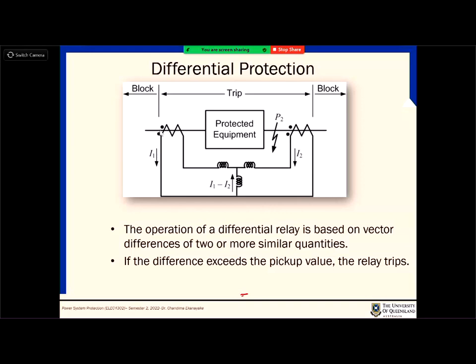So you can see that there are some dots here. The reason is that when you connect a transformer in, let's say, the reverse direction, there is a 180 degrees phase shift of the current. So we always want to connect both of these CTs in a way that the addition of these currents will give you 0, right? So that basically I1 and I2 are equal, which means I1 minus I2 is equal to 0 if there is no fault. If there is a fault, you can see that a current I1 minus I2 flows between these two. Otherwise, this I1 goes through this secondary, is equal to I2 coming back to this CT, so that both currents will be equal.